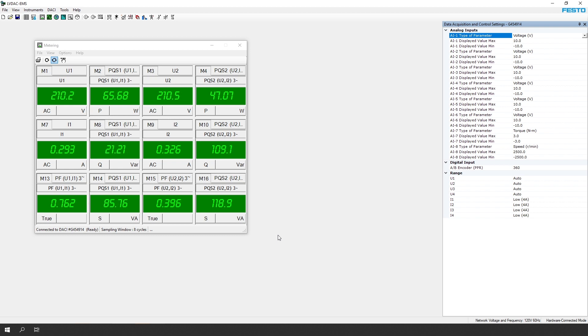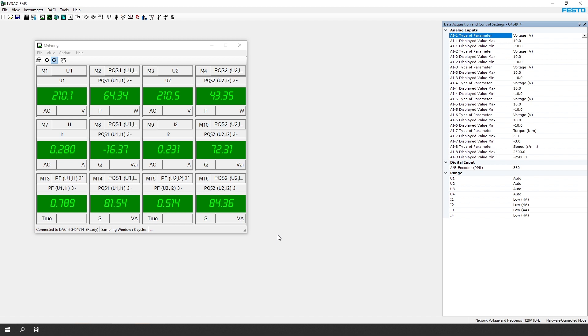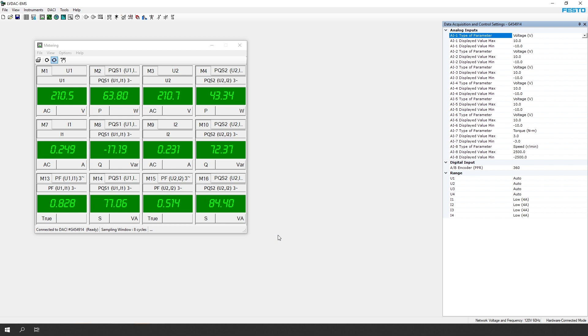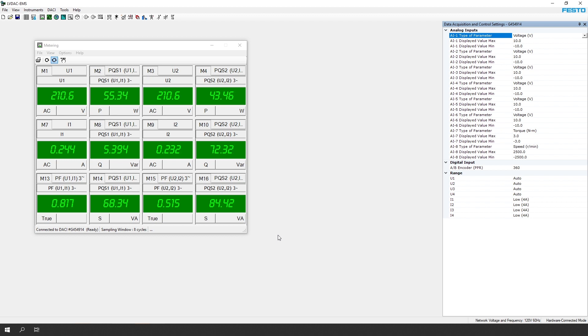Now if we make a change on the load by decreasing the inductive load, you will see the impact on the power factor on the load side, which has jumped up to 0.5. Currently, the power factor correction module is about to remove a bank of capacitor. And now it just removed it, so we can see that our new power factor is 0.83 on our LVDAC software.